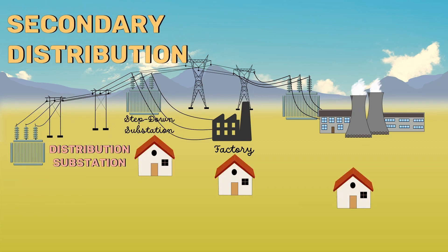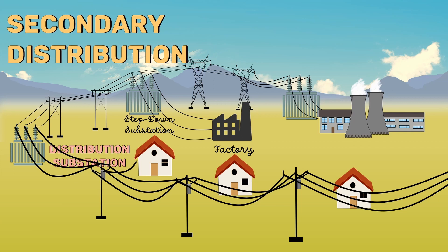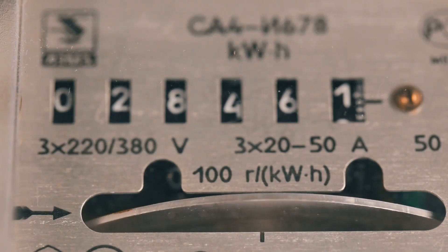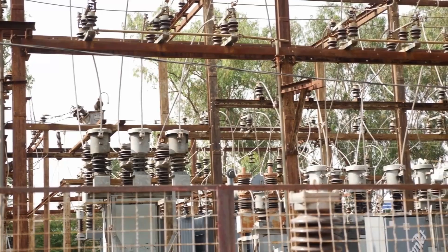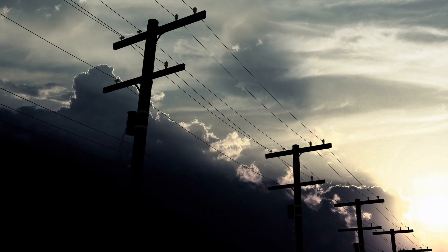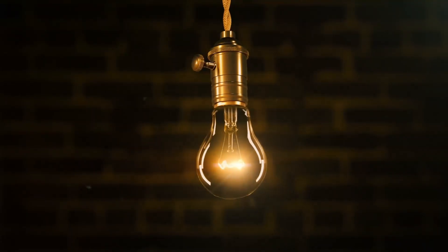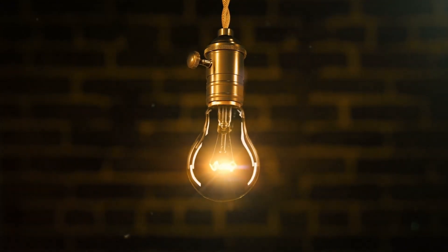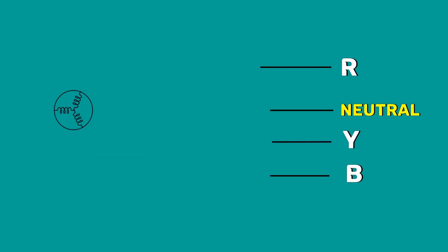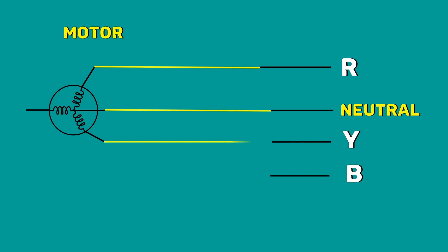The secondary distribution system is the part of the AC distribution system which includes the range of voltages a normal consumer uses. It is operated at very low voltage level, which is typically equal to the voltage of electric appliances. The distribution substations are located near consumers' localities. Here, the voltage is stepped down and is carried out by a three-phase, four-wire system. The single-phase domestic loads like lamps are connected between any one phase and the neutral, whereas three-phase motor loads are connected across three-phase lines directly.